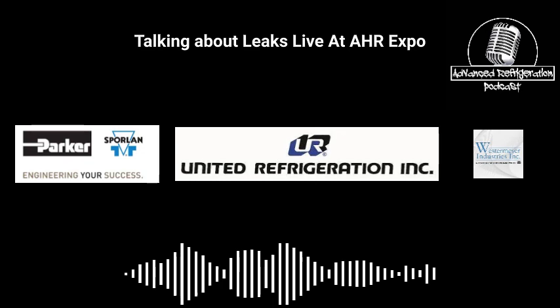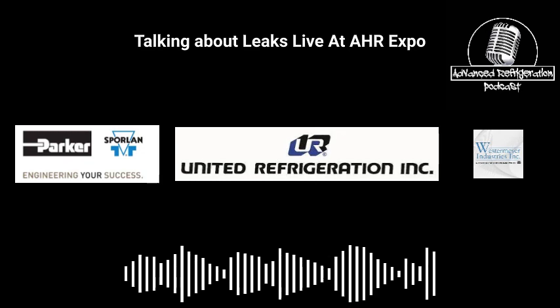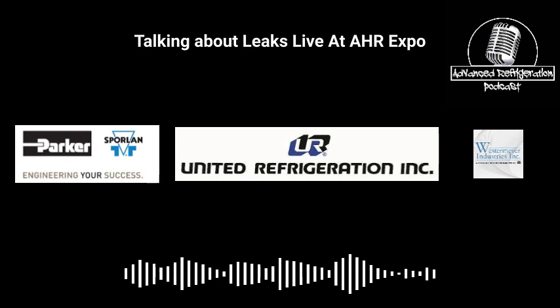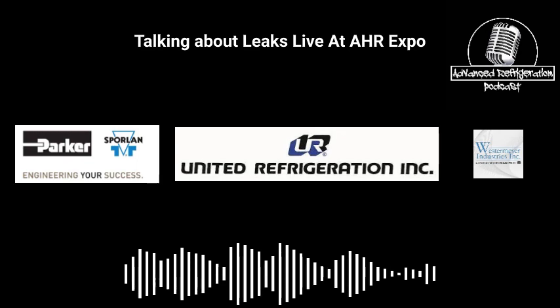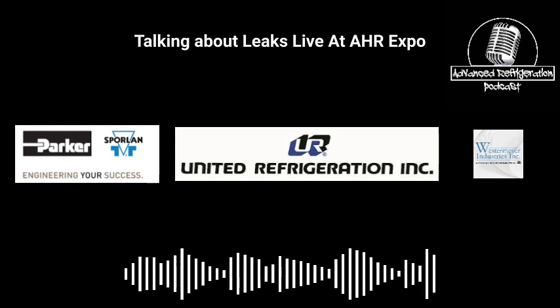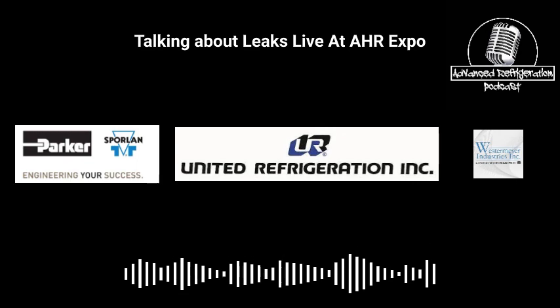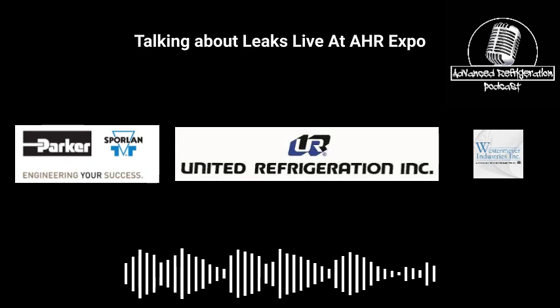Now let's talk about the other side of it, the leak side. Now, CO2 leak detection has increasingly become more difficult. So it's gotten better, but go ahead. So let me just start off by saying CO2 leak detection is a little bit more difficult than typical regular leak detection. The only reason is because CO2 in the air is typically anywhere from 300 to 400 parts per million. If you're in a classroom or an office area, it'll be as high as 600 to 800. So unless you're in a rack room all by yourself, it's hard to mitigate. Like, did someone breathe in my general vicinity, or do I have a leak somewhere, right?